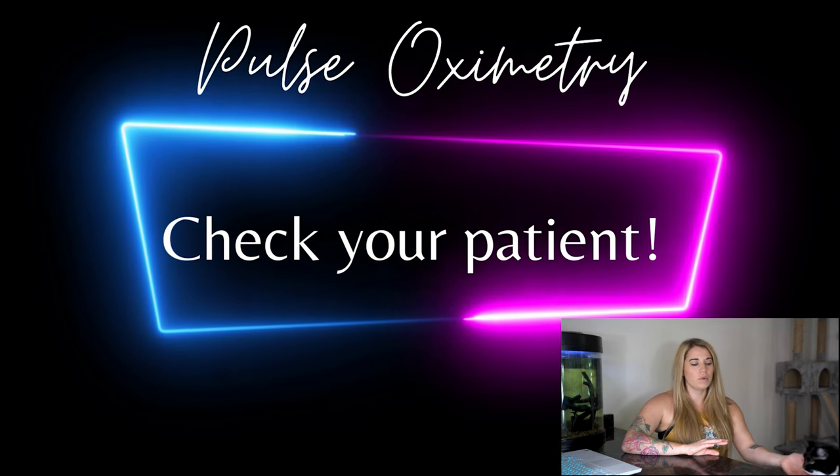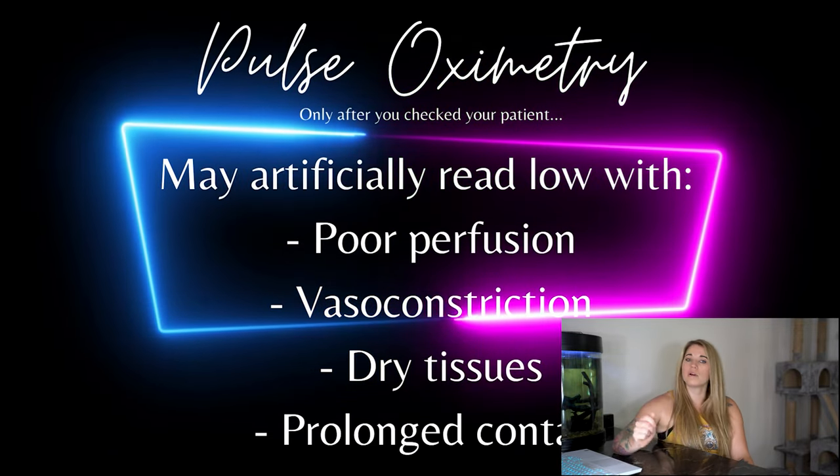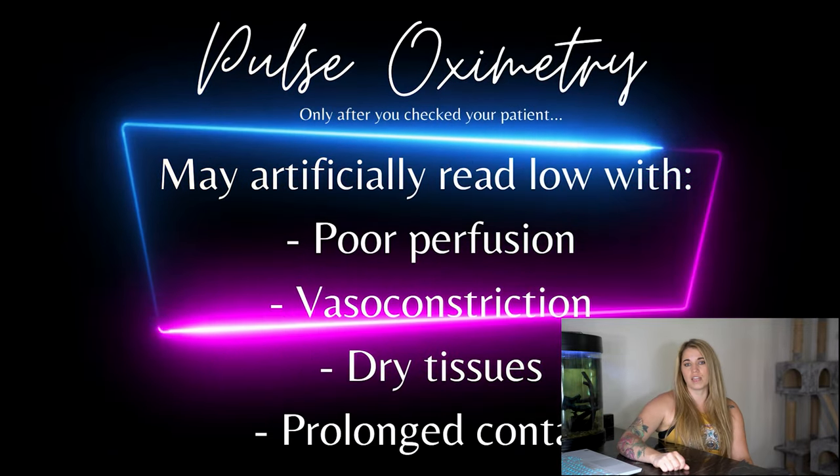The probes tend to read incorrectly in animals with dry tissue, after the probe has been in the same place for an extended period of time, or if they've had medications that can cause vasoconstriction. Things you can do to get your pulse ox to read more appropriately: put a wet gauze between their tongue and the probe, and make sure you move the probe around frequently throughout your anesthetic procedure.